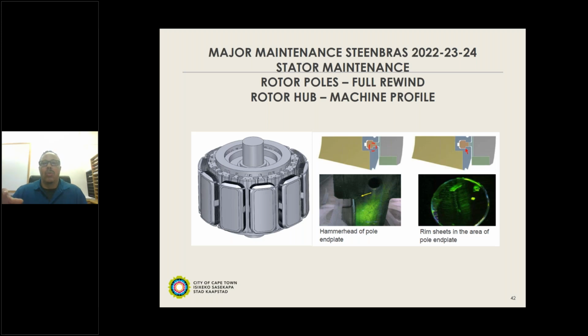Normally we would just do the welding maintenance and then the NDT checks, but because the insulation had given up the ghost after all these years, we were forced to do a full rewind of all the poles. In addition, over the years, because a lot of the major rotating parts are metal, there's been metal fatigue, so we've had to keep a close eye on that.